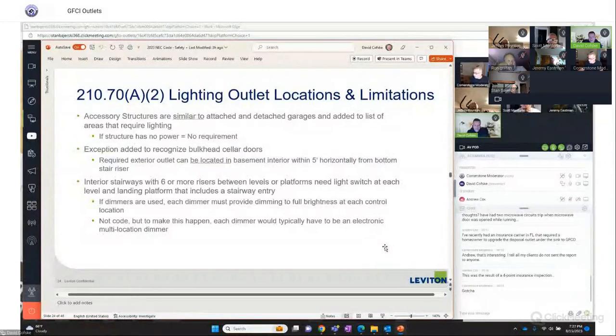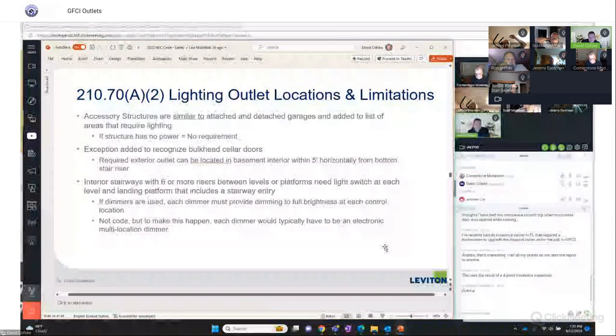This is another one that's in the code that came up. And again, it makes perfect common sense, but it's definitely a safety thing. So what the code is under 210.70 saying is that any detached garage or an attached building basically needs to have, and they basically say if the structure has no power in it, you don't have to do anything to it, but if it does, it basically wants lighting outlets within the area.